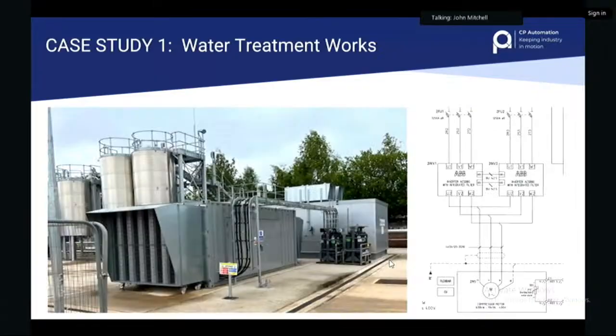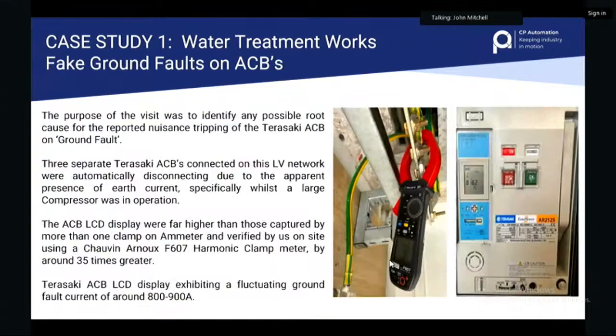So why don't we show you a few cases we've solved problems for. This is a compressor for a water treatment plant - two ABB drives back to back, controlling a 630 kilowatt compressor. The drives were low harmonic, and what they were doing was creating a common mode noise that was affecting the Terasaki ACB. The ACB thought it had a ground fault of 816 amps. It wasn't real - the electrical noise was tricking the sensor into thinking it had something that wasn't there.